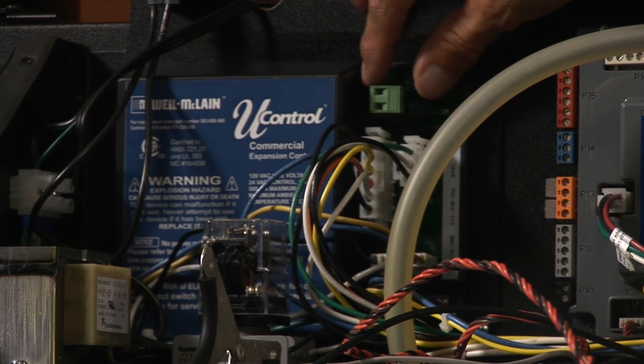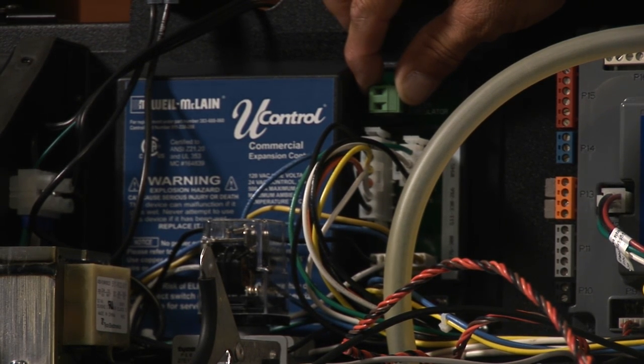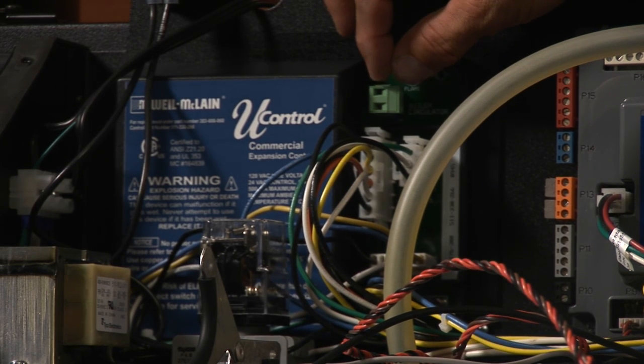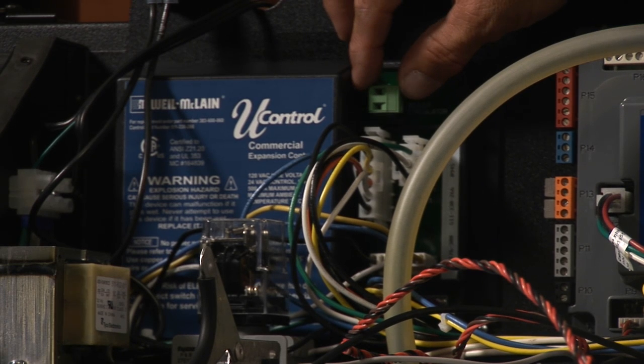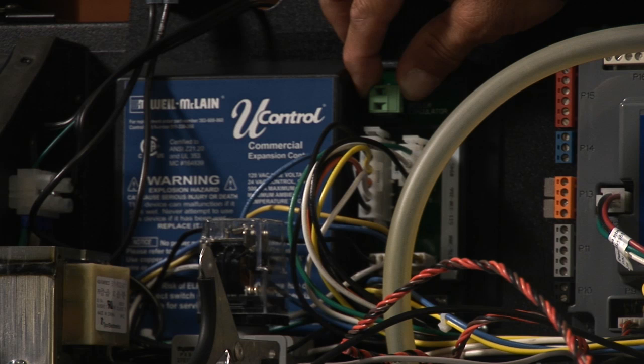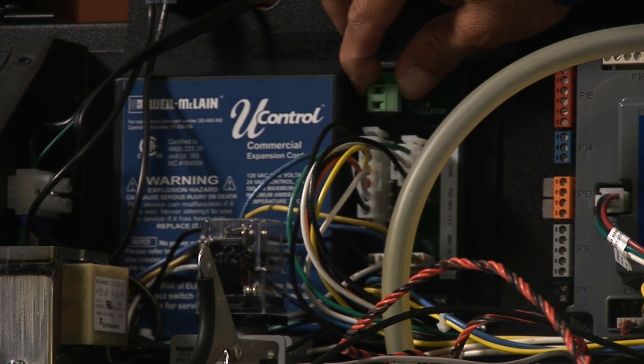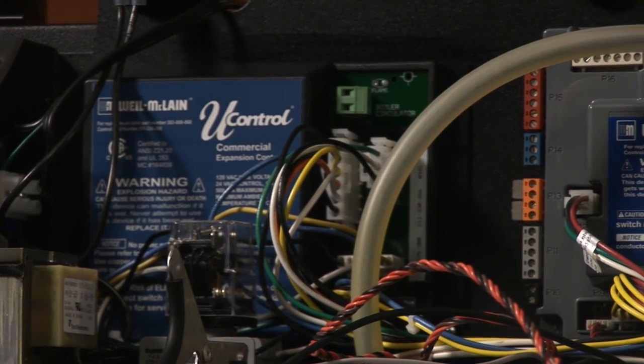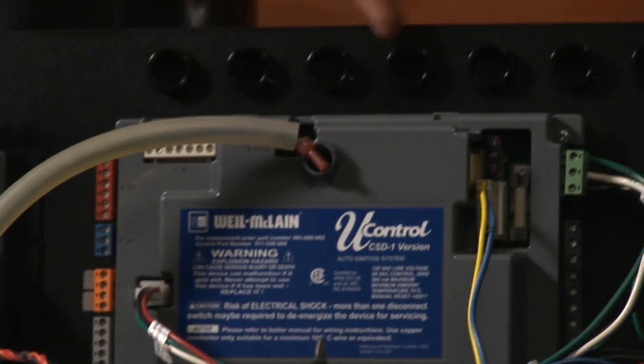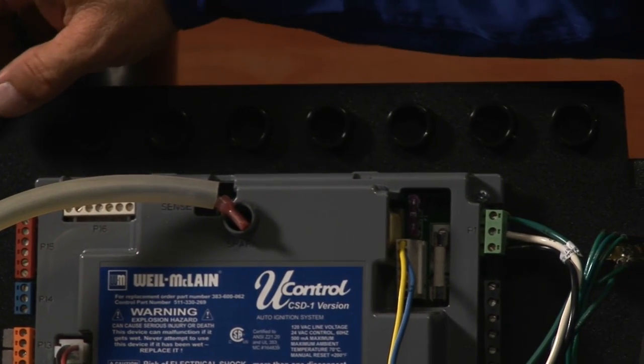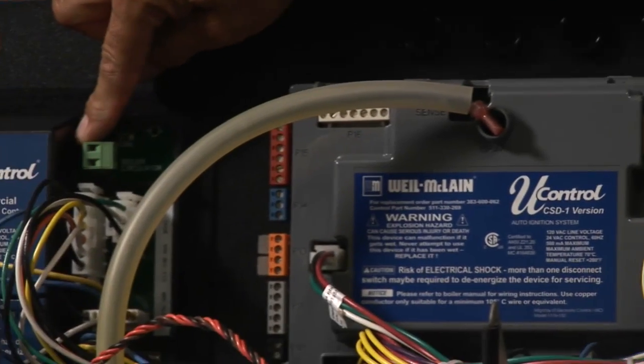So this circuit is isolated strictly for the boiler pump. So this is power in and power out to the circulator on the boiler for the boiler pump. That is pump number 4. That's your first power circuit coming to the boiler. Across the top, we have all the knockouts for your electrical circuits. One electrical circuit is going to come in to power this pump only.